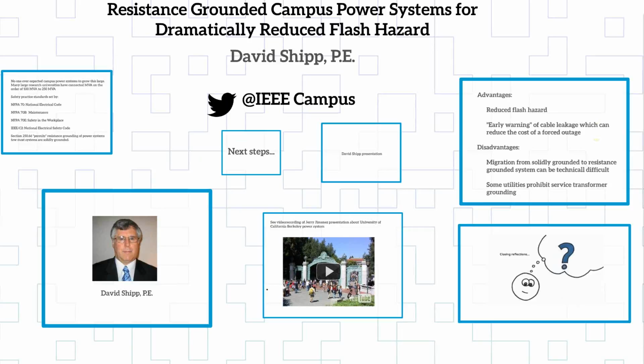The bottom line is, if we can get some of them to do it, they're going to start seeing a significant difference, and it's going to be economic on the replacement cost. It's going to address your reliability. It's going to lower your exposure risk to people for the incident energy. And ultimately, 5 years from now, it's going to cost you a lot less. But again, what do I got to do to change it and do it? Obviously, if we start off from a new design system, you could work it out.